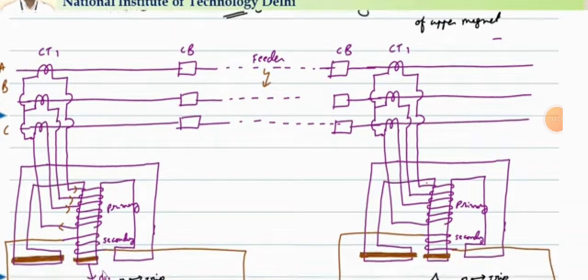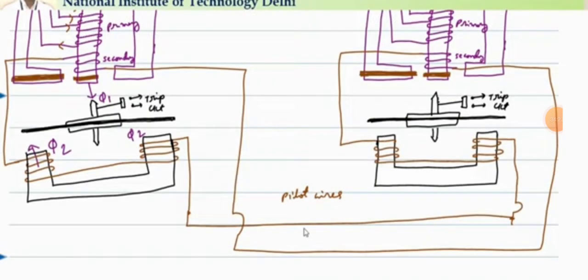This method is used for pilot wire loop resistance of up to 800 ohms. Above that, because of the increase in resistance value, the circulating currents decrease drastically and the torque is not sufficient to operate the relay. That is why this is used up to 800 ohms only.